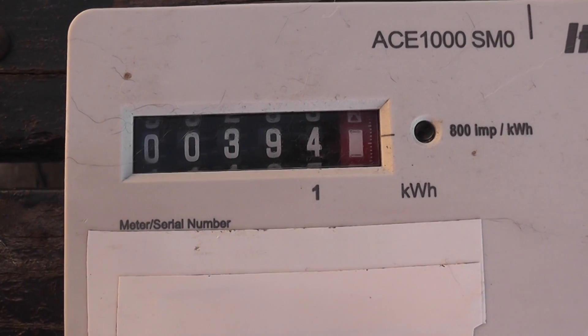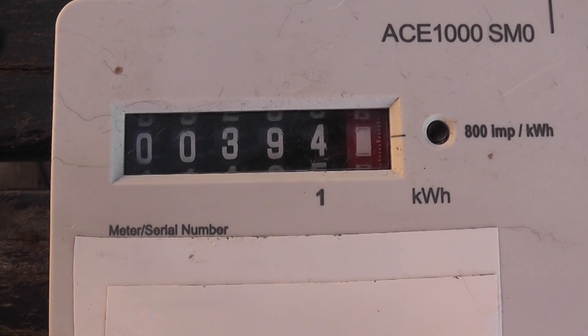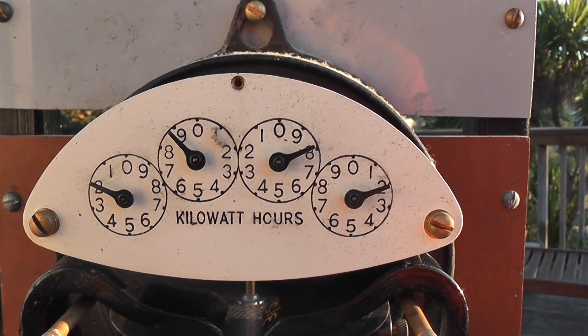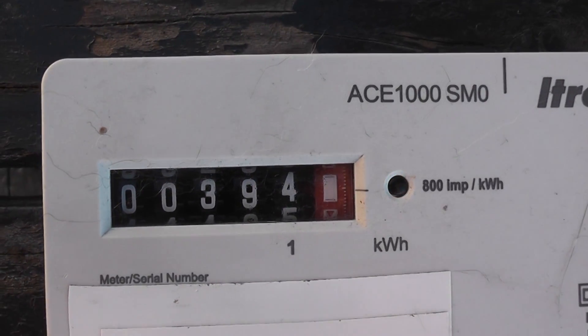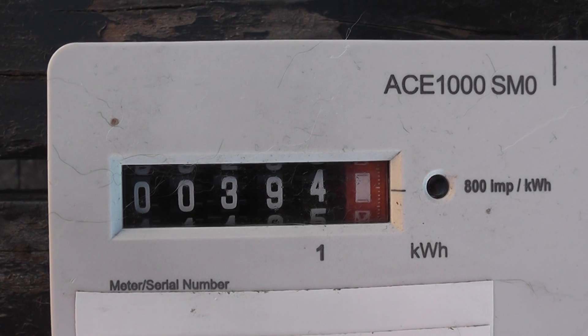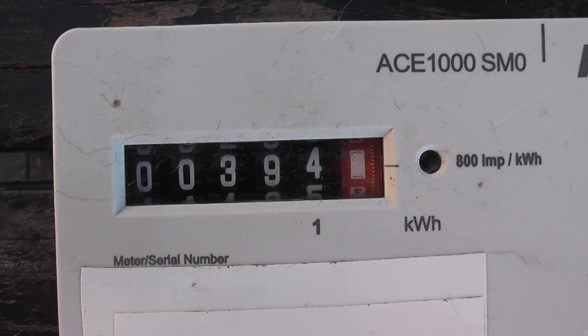The hourglass on the check meter is full now so it should flick over, and then I'll do the start of the dial test. The reading is now 1882 exactly, which lines up — that's 0.9, about 0.92 because the number is just about to flick over. So let's roll and see how the accuracy goes.